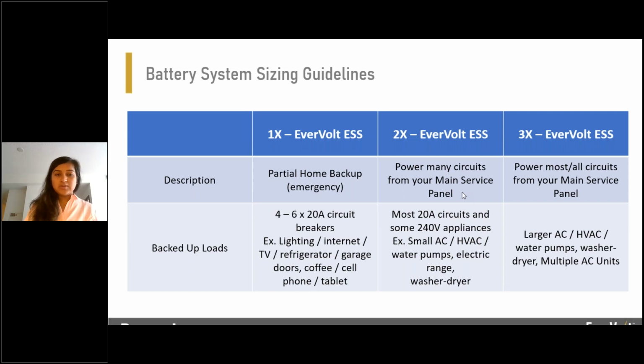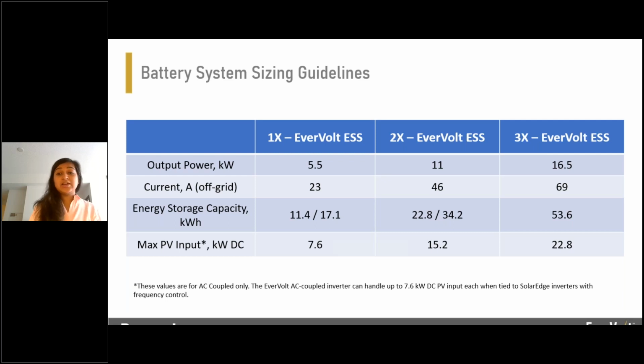The way the calculation is done is based on the maximum output current, which is determined by the inverter size. Because it's a 5.5 kilowatt continuous output power, that would roughly translate to 23 amps continuous. This slide shows the numbers used for these calculations in detail, where the maximum continuous current during a backup situation is 23 amps for a single system. Based on how many appliances you connect, that would be the required current rating of the storage system as well. So if the customer wants more backup appliances, then more inverters need to be stacked.